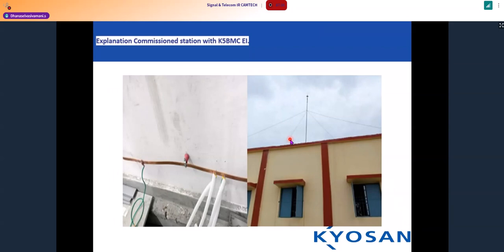And this is our earthing arrangement. The Class A should be provided as per the RDSO standard, and it should be connected to one or two earth pits. The one or two earth pits should be different from our EA room earth. The EA room perimeter earth or ring earth should be different from that, and both earths should be interconnected. And when it comes to the room, it should be individually connected, and it should be welded properly.